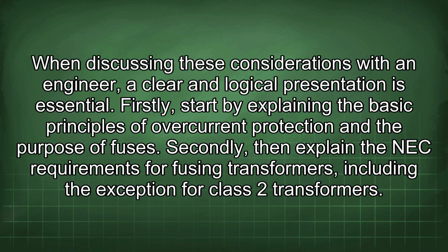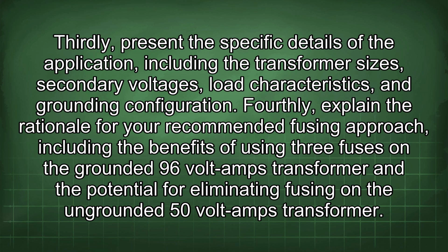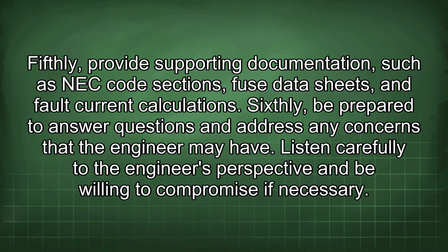When discussing these considerations with an engineer, a clear and logical presentation is essential. Firstly, start by explaining the basic principles of overcurrent protection and the purpose of fuses. Secondly, explain the NEC requirements for fusing transformers, including the exception for Class 2 transformers. Thirdly, present the specific details of the application, including the transformer sizes, secondary voltages, load characteristics, and grounding configuration. Fourthly, explain the rationale for your recommended fusing approach, including the benefits of using 3 fuses on the grounded 96 volt-amp transformer and the potential for eliminating fusing on the ungrounded 50 volt-amp transformer.